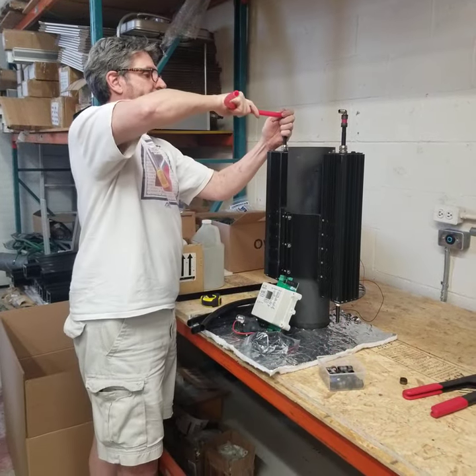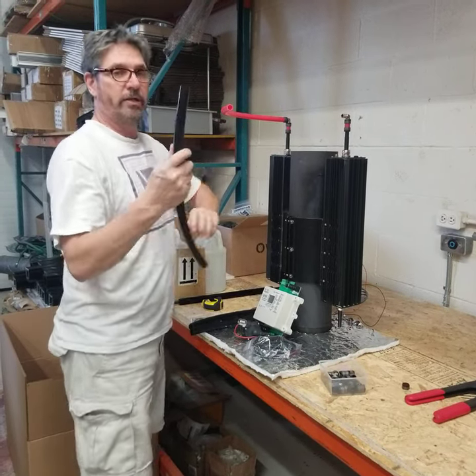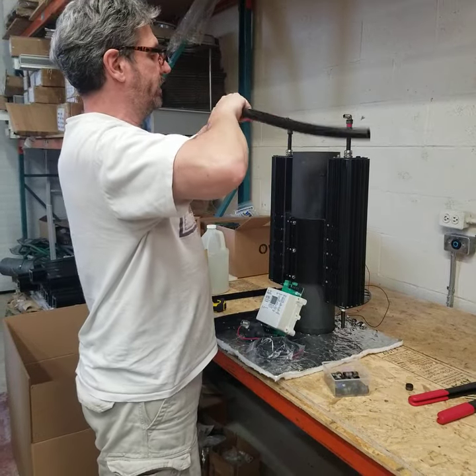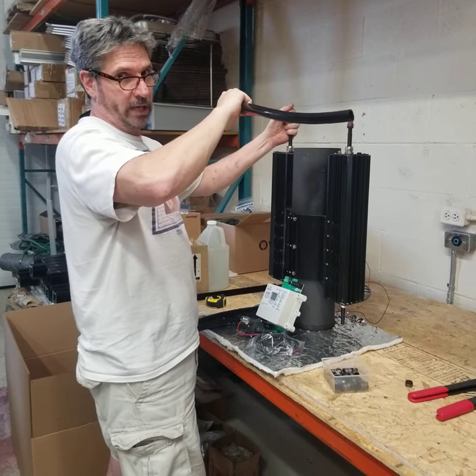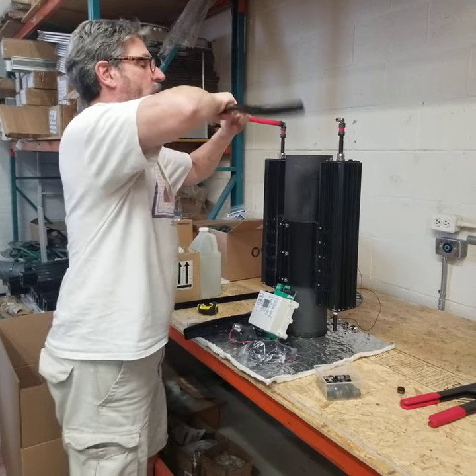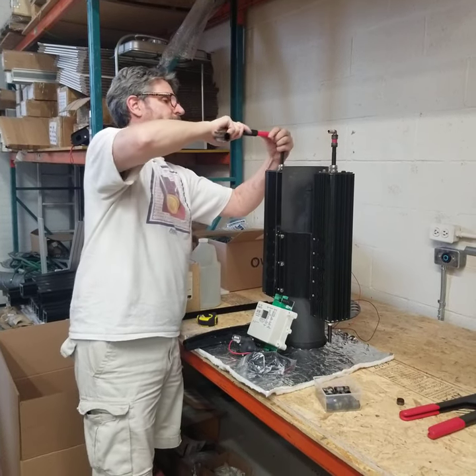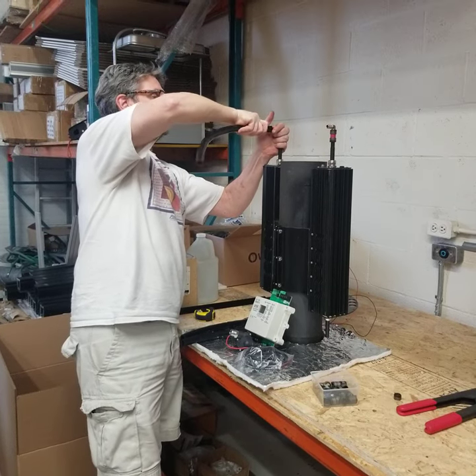We then add our tube — we'll give you the length of this tube, not supplied. What we do supply is a sleeve. This is a silicone high-temperature sleeve. It's not strictly required because cold water is going through here most of the time, or relatively warm water up to maybe 120 degrees Fahrenheit. This sleeve slides over the PEX, protecting it as a secondary means of protection. It's a tight fit, so it'll take a little bit — you might use a little bit of grease just to get it on.